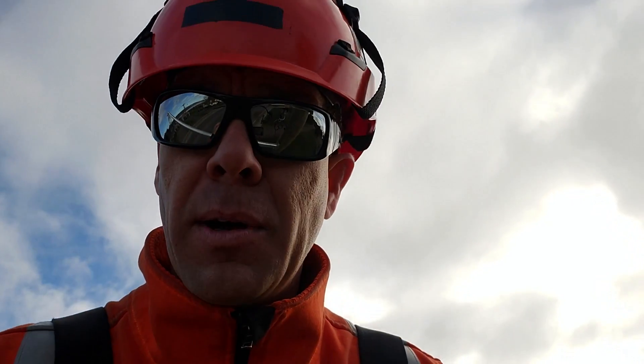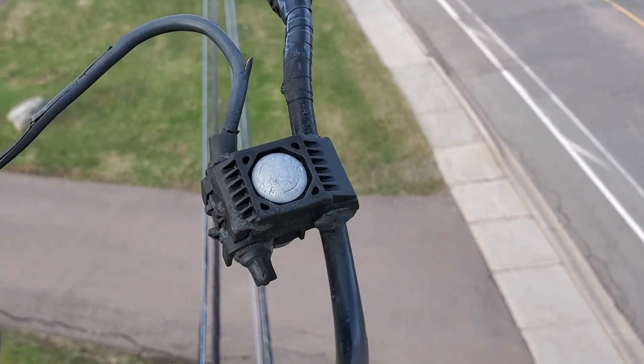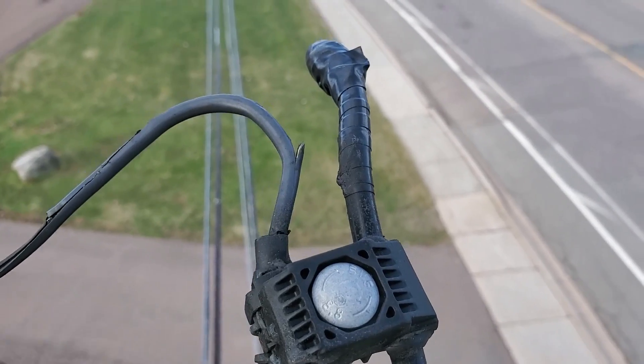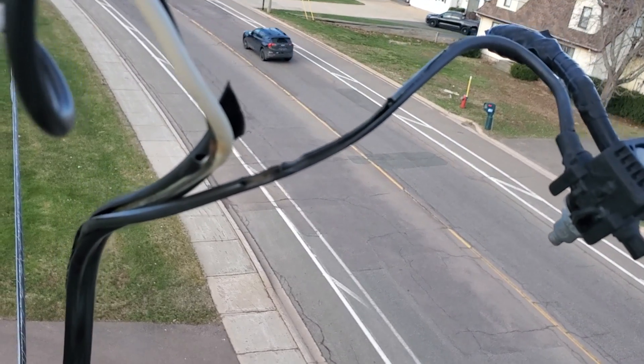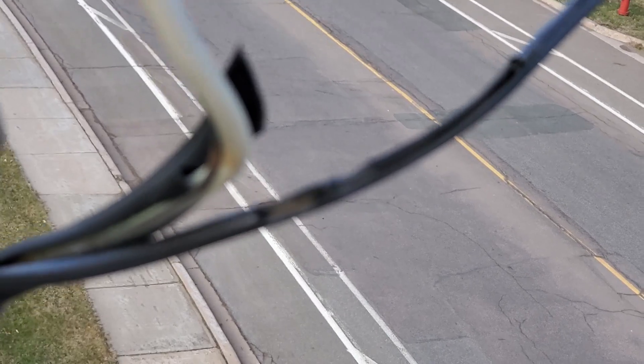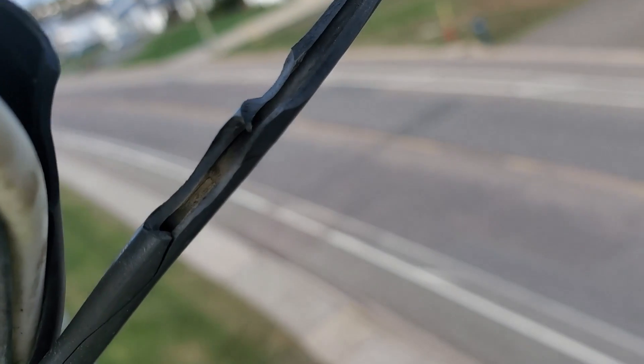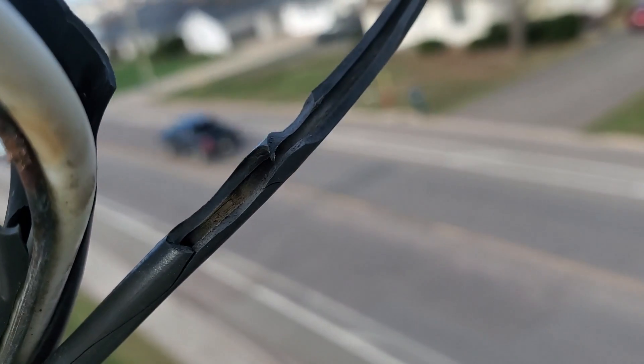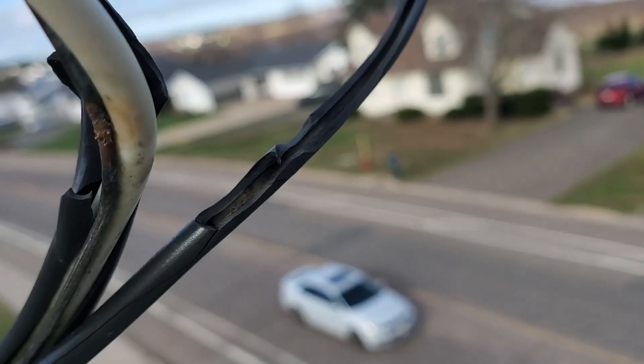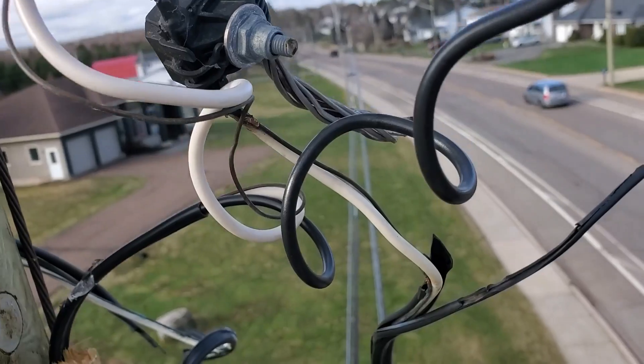This guy will be fit for the dumpster. Just before we go, as I went to remove the hot connector I noticed something else pretty wild. This is our 120-volt wire — you can see there's a piercing connector which energizes that streetlight wire. And we can see right inside the sheathing of the wire — the wire inside that jacket is just gone. That 14-gauge wire: 7200 volts completely disintegrated it. So I will have to run all new wire for these lights as well.